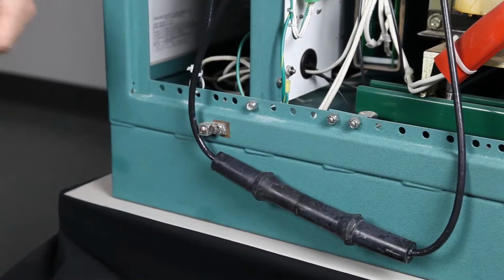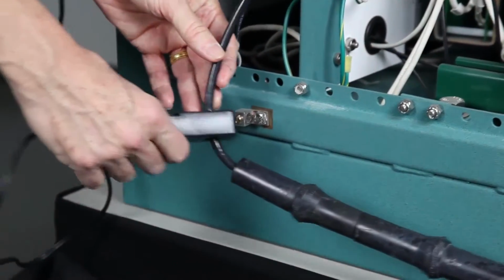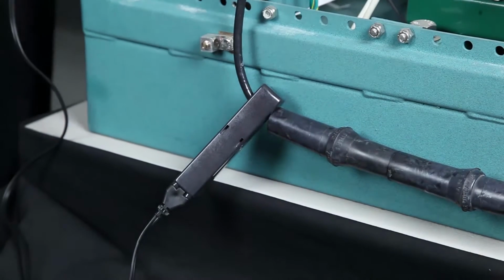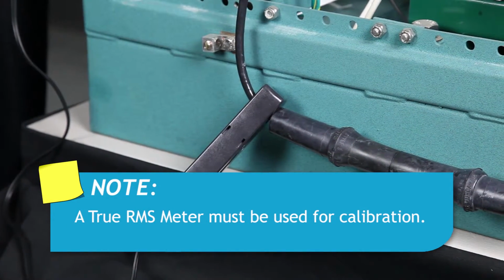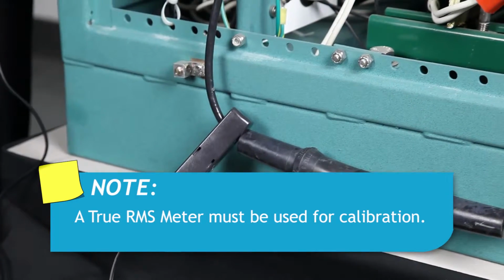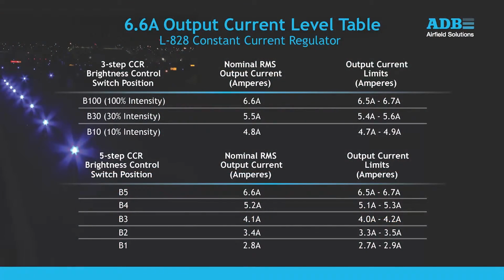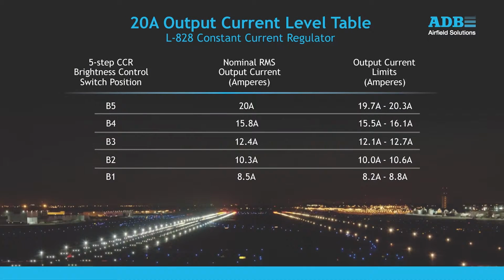Next, attach a true RMS meter with current clamp around the series circuit wire. Since the output current of the regulator will not be a true sine wave, a true RMS meter must be used. Refer to the tables on screen for the nominal RMS output current levels for a 3-step 6.6 amp regulator and a 5-step 6.6 amp regulator. This screen shows the nominal RMS output current levels for a 5-step 20 amp regulator. 20 amp regulators are manufactured only as 5-step.